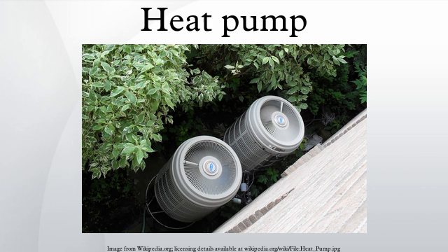Heat pumps using R134a are not as efficient as those using R12 that they replace, and therefore more energy is required to operate systems utilizing R134a than those using R12. Other substances such as liquid R717 ammonia are widely used in large-scale systems, or occasionally the less corrosive but more flammable propane or butane can also be used. Since 2001, carbon dioxide, R744, has increasingly been used, utilizing the transcritical cycle, although it requires much higher working pressures.